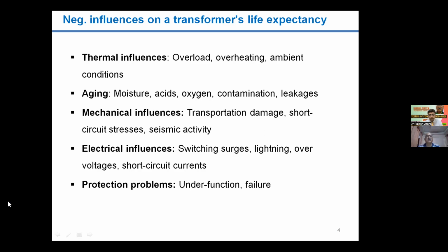inside of the tank. Then mechanical influences, meaning when we transport the transformer from one side to another, or many times when in operation, due to through faults or heavy through faults, deformations may take place because of these kinds of stresses. Then seismic activities may also affect the inside structure of the transformer. Electrical influences like switching surges, lightning surges, overvoltage are experienced by the transformer during its operation time. Then short circuit currents, as I mentioned earlier also, through faults are quite common on the transformer. This means the fault is outside the transformer on the feeders emanating from the transformer. So these are also experienced by the transformer.